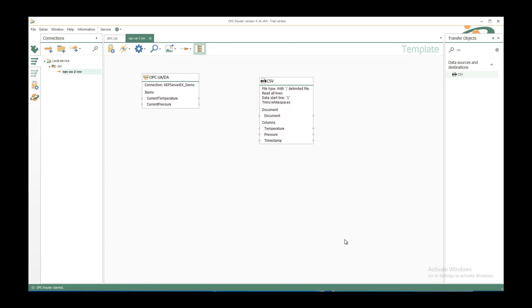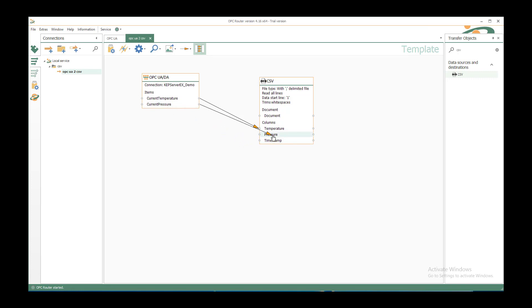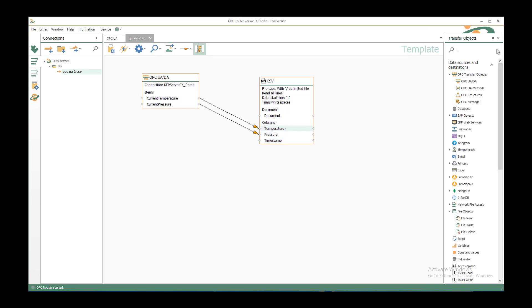As column names I use temperature, pressure, and timestamp. I don't have to configure the data type, it will automatically be string in the target document. I connect the current temperature by left clicking on the item and leaving it over the target element temperature in the CSV column. And the current pressure will be connected to the pressure. In this case we use the timestamp out of an OPC router variable that is always predefined.